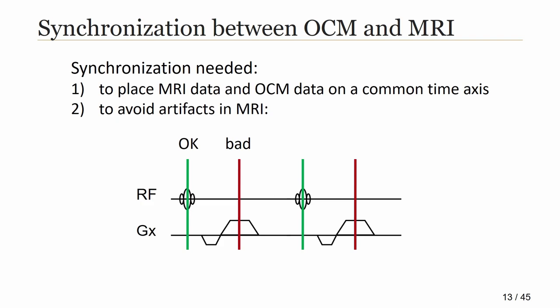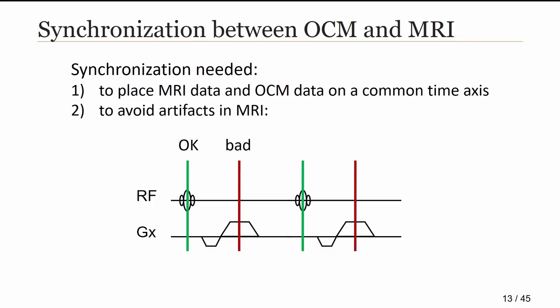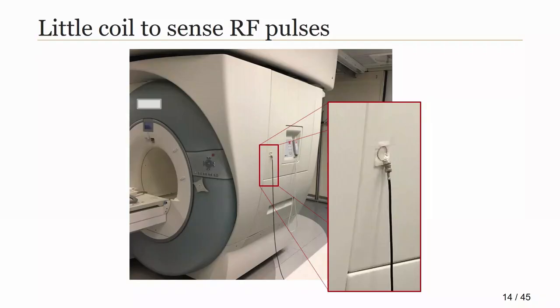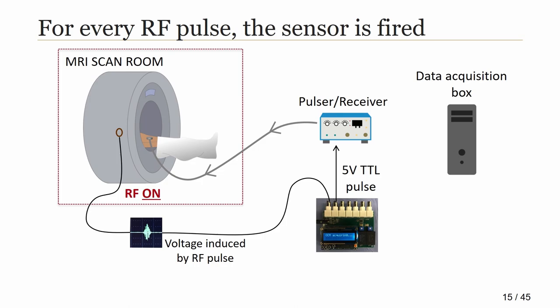It's important to synchronize those two streams of data so that both the MRI and the OCM data are on the same time axis, enabling joint reconstruction. We also want to avoid artifacts in MRI — if we were to fire the sensor during a readout window, that would create artifacts. So what we do is detect the RF pulse, and that's when we fire the sensor. We detect the RF with a small coil placed on the outside of the scanner; when an RF pulse is sent, we detect the weak signal, which gets converted through a pulse receiver into a TTL pulse that triggers the sensor. The pulse receiver then switches to receive mode and passes the returning signal to the data acquisition system.